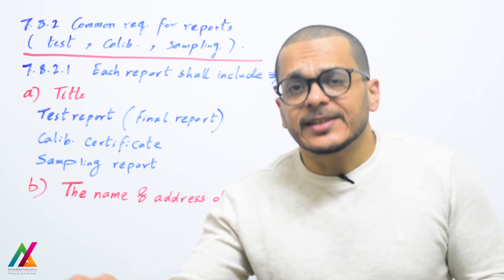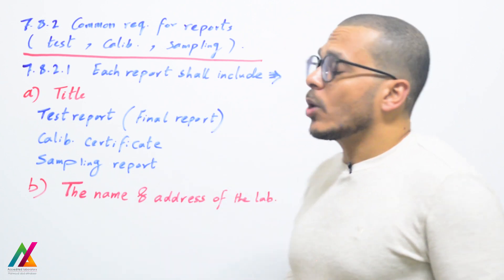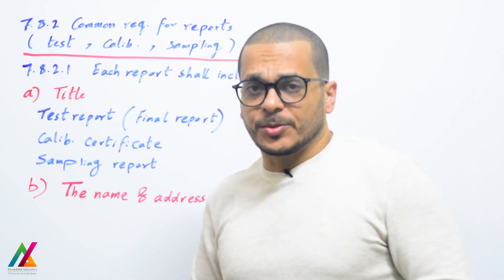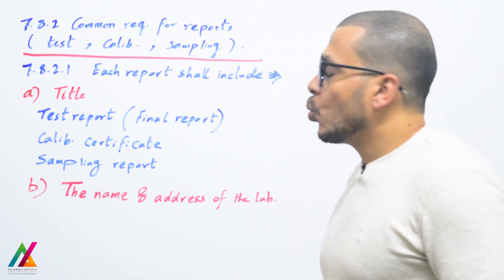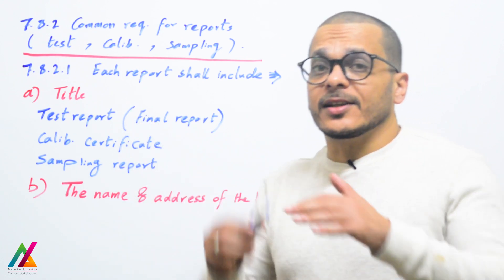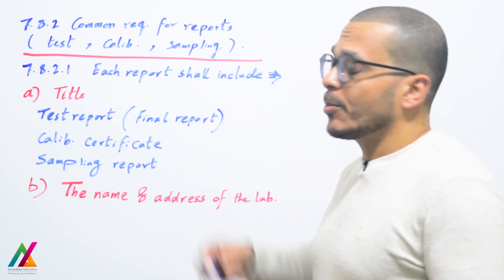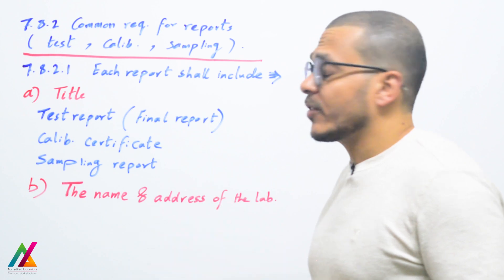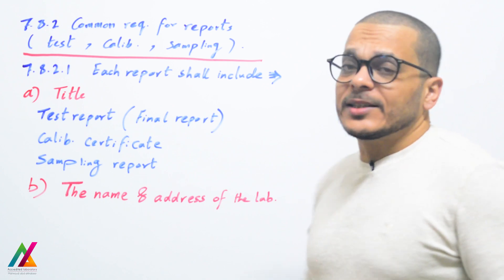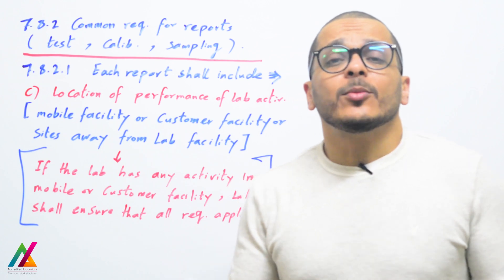We have common requirements for reports: test reports, calibration certificates, and sampling reports. Clause 7.8.2.1 states that each report shall include the following: a title at the beginning — whether it is a test report, calibration certificate, or sampling report — the name and address of the lab, and also the location where the lab activity was performed.